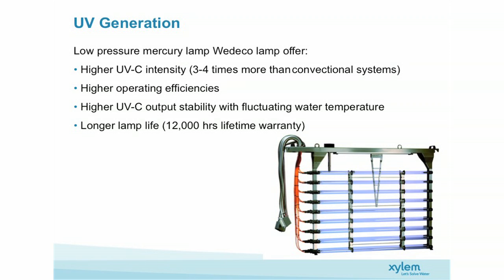So, UV generation, this is how it looks. It's a series of lamps. They look like your fluorescent tubes. Wedeco uses low pressure lamps, which basically have a very small bit of mercury sitting on one side of the lamp, and they then pass an energy current through the lamp, excite the mercury, and you get the mercury vapor, which gives you the UV light. Same as the fluorescent system.